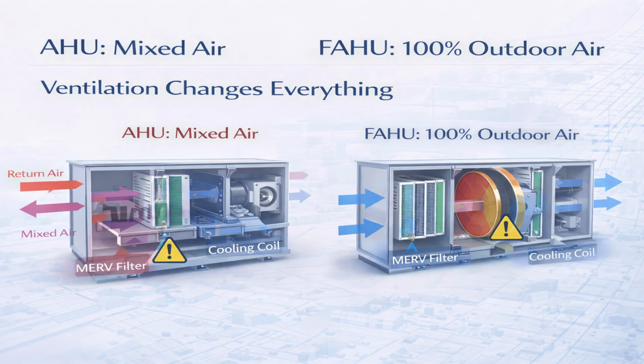Coils must be sized not only for the temperature reduction but for effective moisture removal. Filtration stages usually need to be more robust, increasing pressure drop. Fan power requirements rise due to higher airflow resistance. And energy recovery systems often become essential to control energy consumption. When a FAHU is treated like a regular AHU, using similar assumptions for coil sizing, pressure drop, or fan selection, the system almost always struggles. This is a very common and very costly mistake. Understanding this distinction is crucial because FAHUs are often at the heart of the indoor air quality, comfort, and energy performance across the entire building.